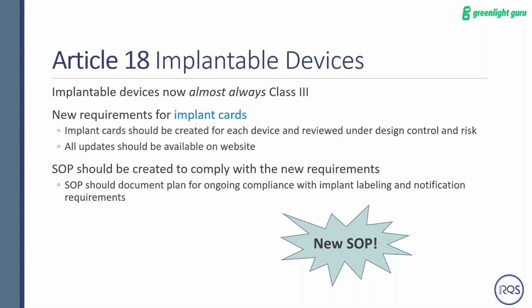These should be created and reviewed under design control and risk to make sure they have all the information, and all updates to this implant card should be available on the website as well as Eudamed. This is going to be a new SOP. If you are making implantable devices, make sure that you have reviewed this section in detail and that you are complying with this in your procedures.